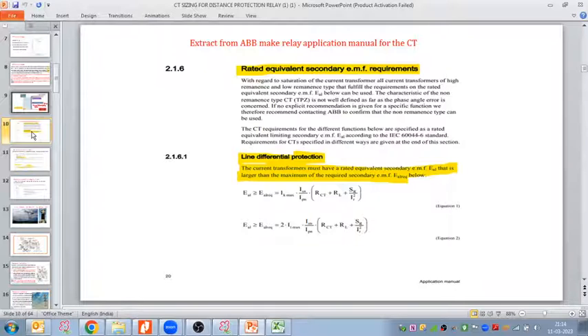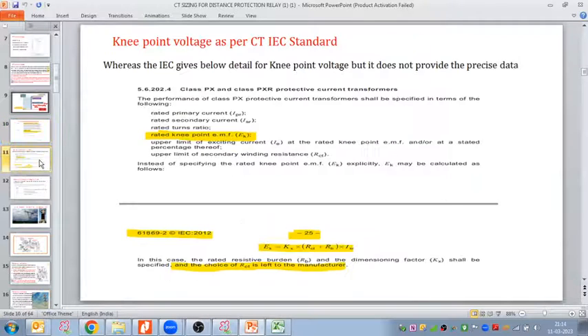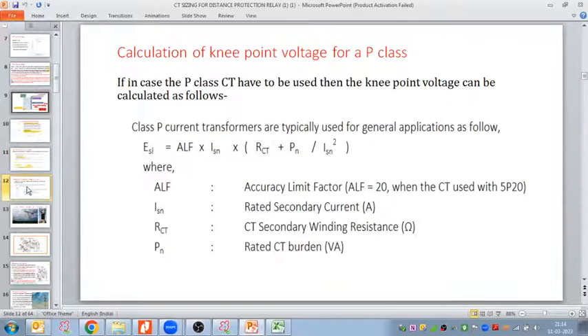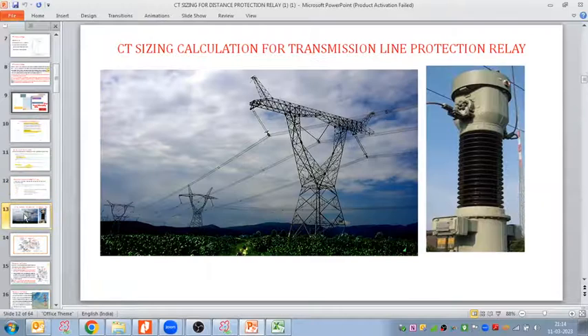Even if you have it in your mind that you will go to the IEC, this is what is given as per the IEC standard. If you want to calculate the knee point voltage for a simple protection class, P class CT, this would be the formula. This we all discussed yesterday.